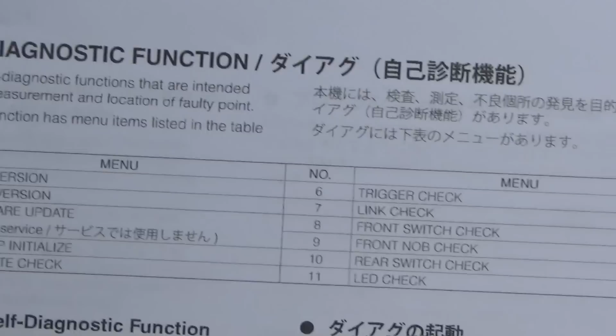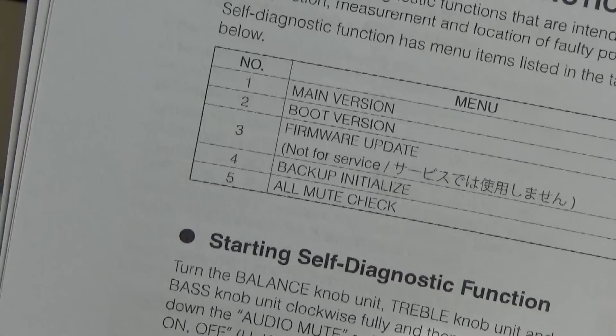That has to do with the firmware and that sort of thing, and I don't care about that. I want to get down to menu number 4, backup initialize, which resets the factory defaults and clears the error code, bringing you back to normal. So I'm going to go to the service manual for menu number 4, backup initialize, right there, and I'll read it to you as I go ahead and do a reset right now.